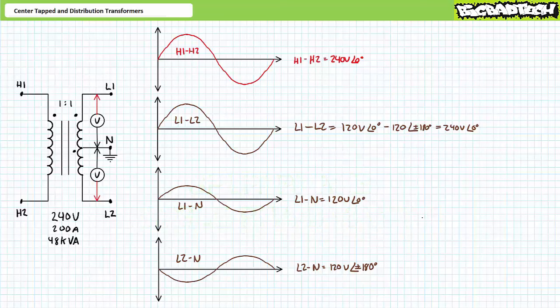240 volts comes into a distribution transformer and it's split into two 120-volt phases — L1 to neutral and L2 to neutral — equal in magnitude yet perfectly out of phase with one another. This type of system additionally allows 240 volts between L1 and L2 for larger electrical loads like water heaters, ovens, dryers, car chargers, and outlets for equipment like welders.